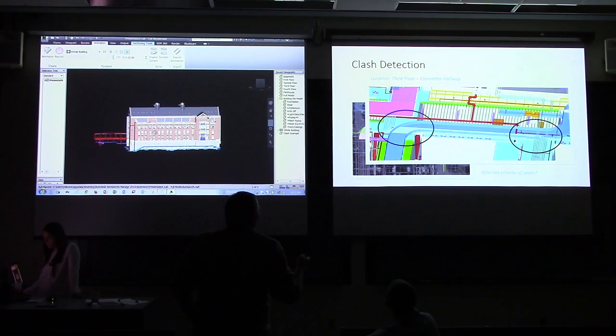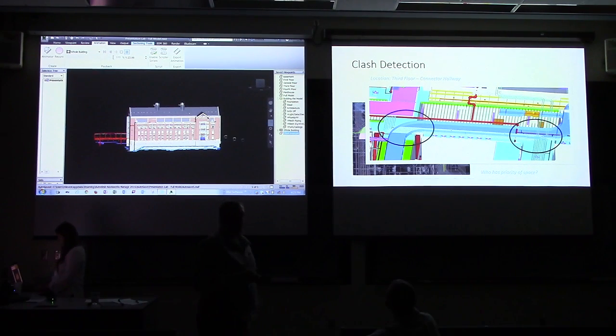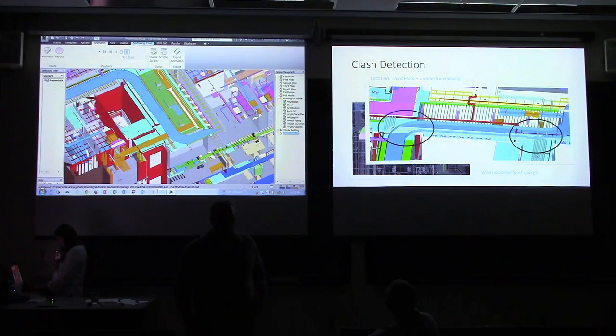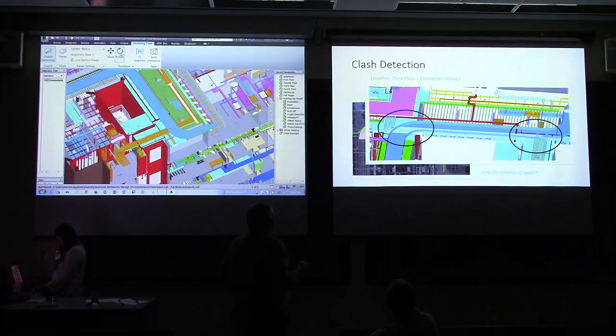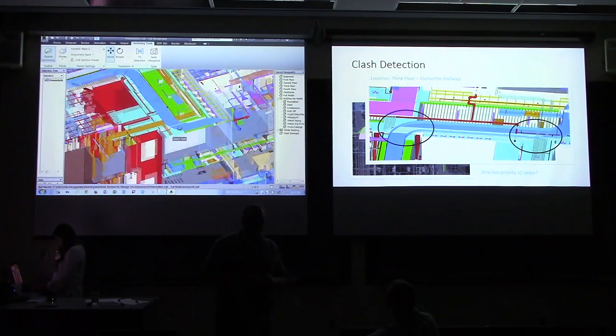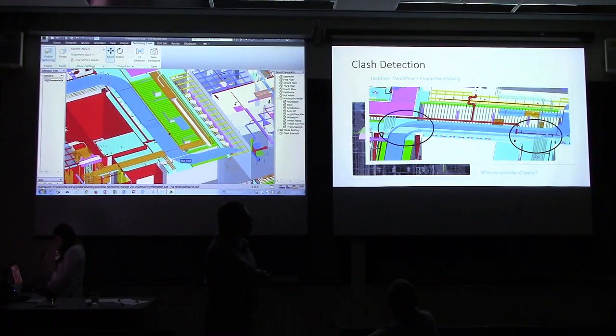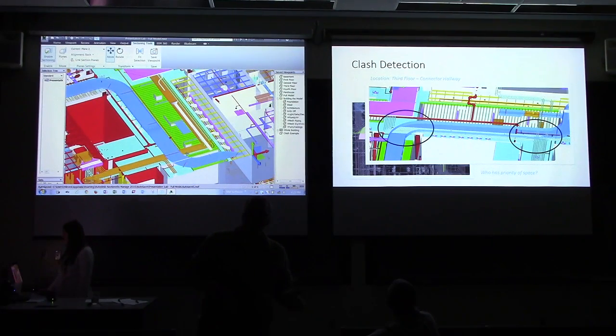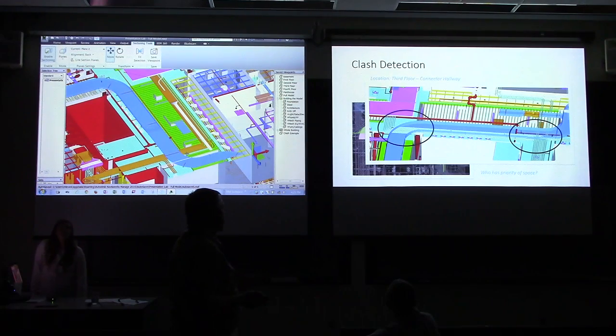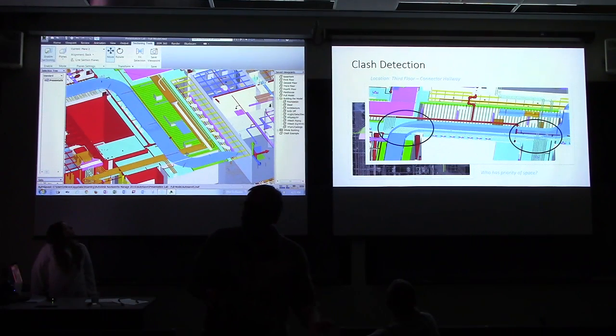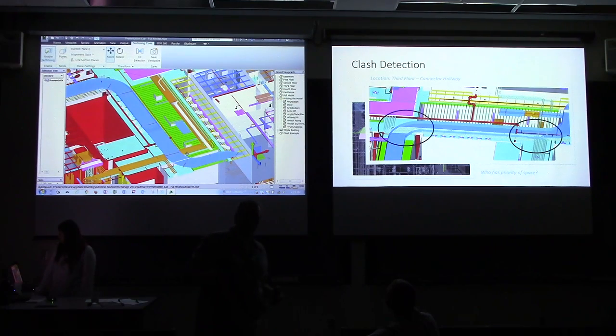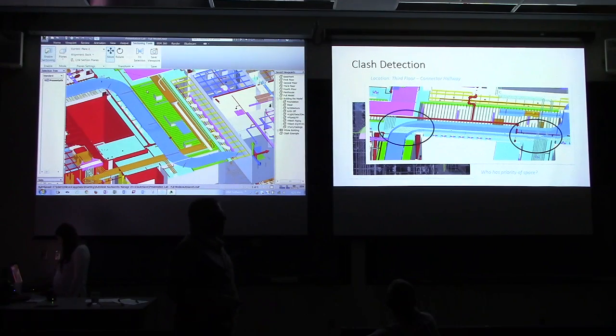In many instances it's not just a lopsided or one-sided approach to a clash, where you just move your pipe. There's a lot of rules, what we call rules of the road, when installing the facilities. For example, drainage piping, anything that's gravity fed, we typically require priority for that system because there's no pressure behind it, it requires gravity to get out of the building. It's pitched pipe, so there's typically only a short avenue to get from point A to point B above a ceiling space.